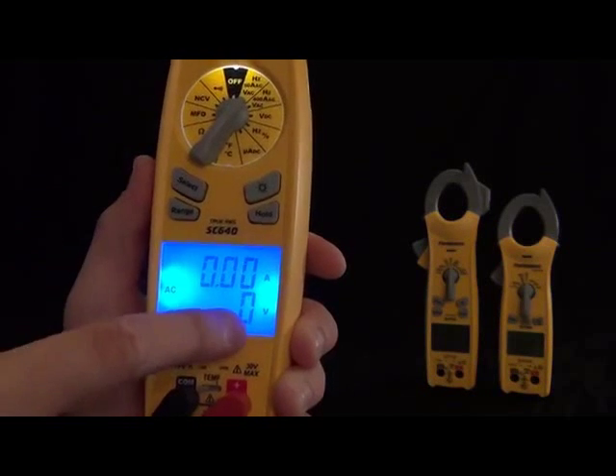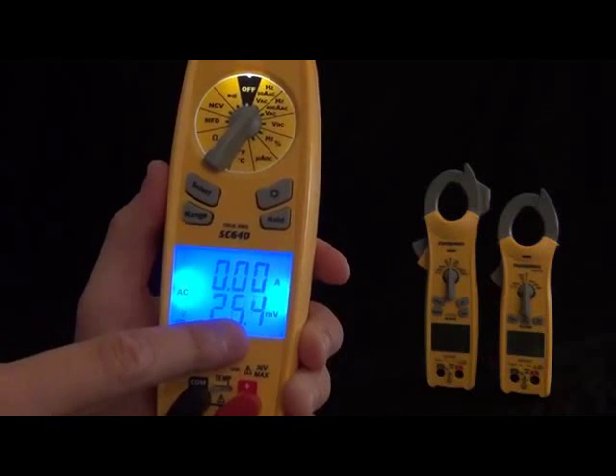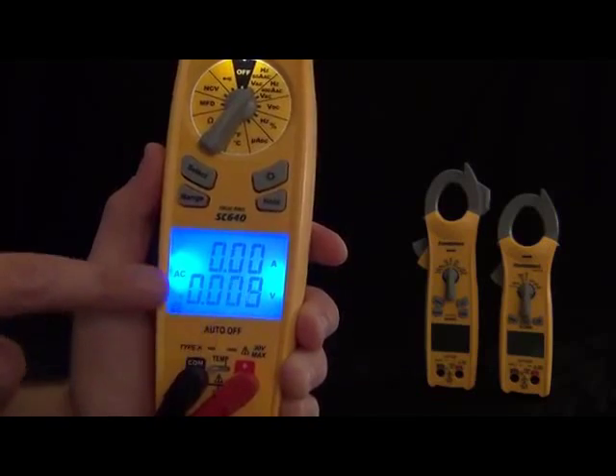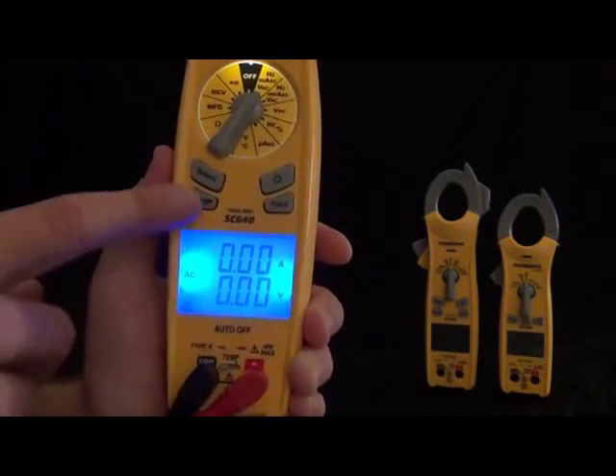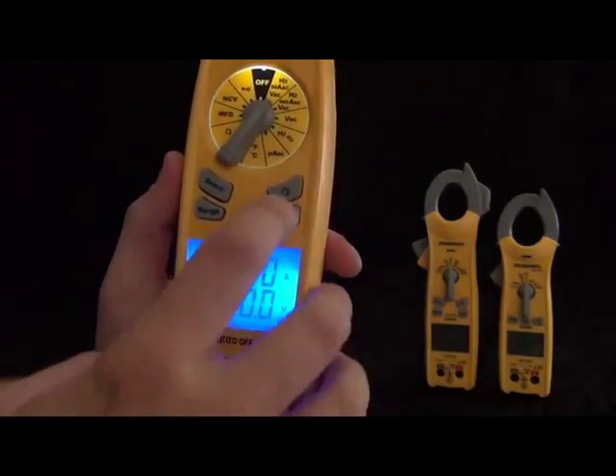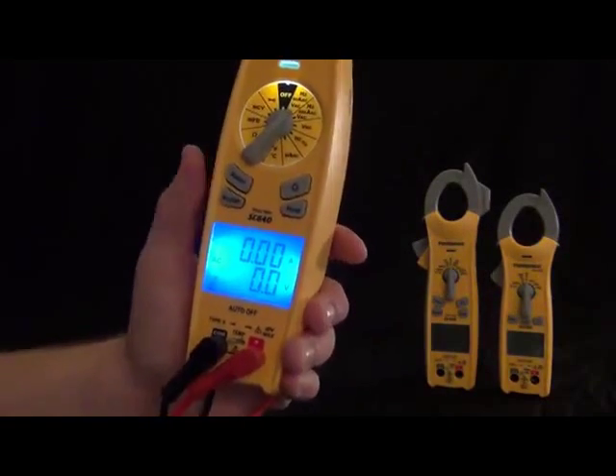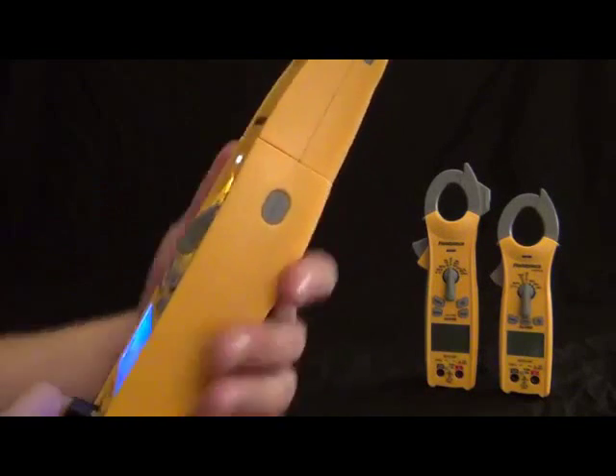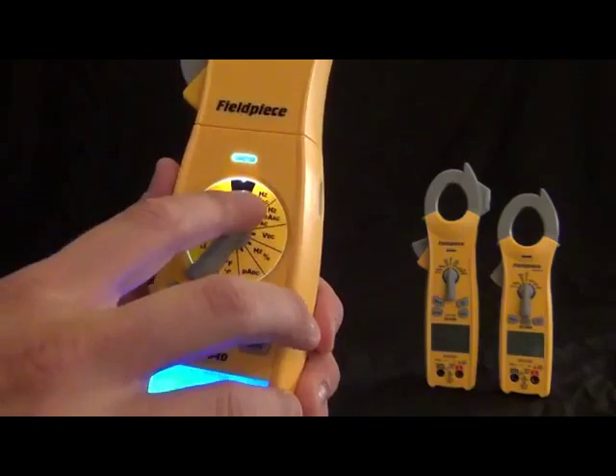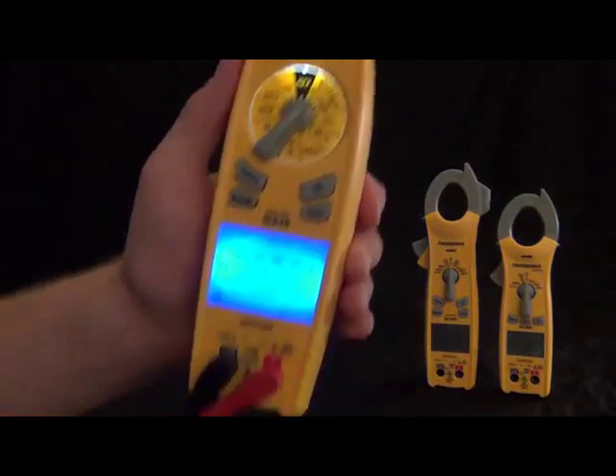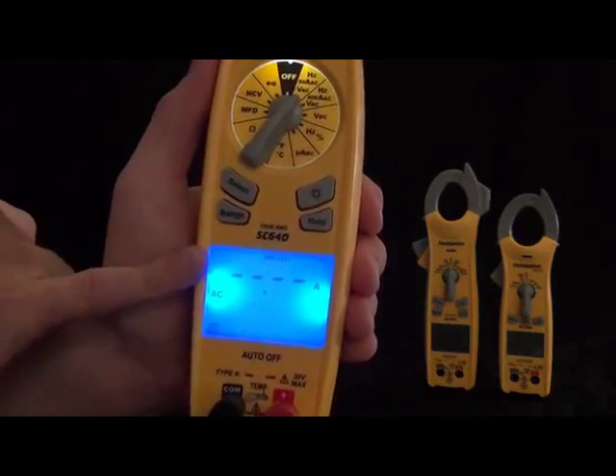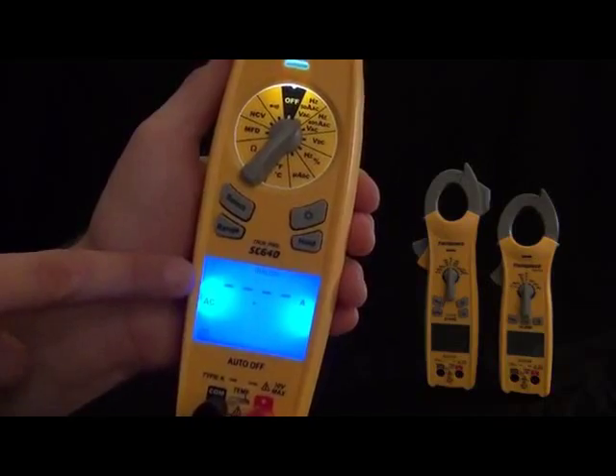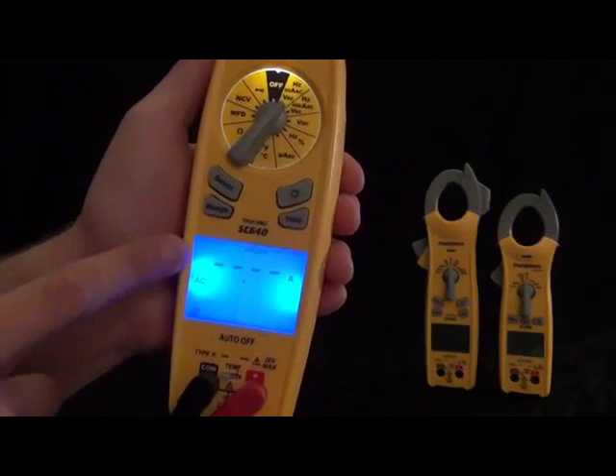And on the side, we have inrush current. So this puts it into inrush mode. So when you're in the amps, the hertz and the amps, either one of these ranges, you can put it into inrush mode. What this is for is when you're doing compressor startups, you can see exactly how many amps it took to get that compressor going, or any motor for that matter. Also, you can also select the range on this by turning the switch position.